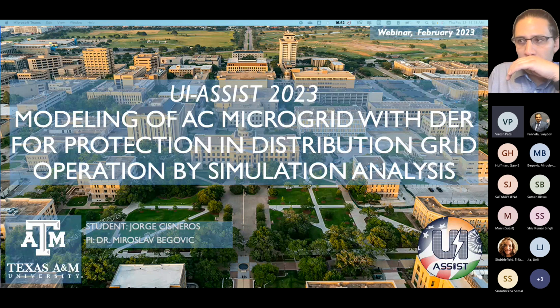Viresh, meanwhile, I see another question from Suman Biswal. He's asking, as the two systems are geographically isolated, does it affect the performance of the simulation? Yes, there was a communication delay, so we had to take care of it. For that, we got a direct connection between the two RTDS using the port binding method. With the number of data packets we tested, we found that 100 data packets was the optimal number, correctly simulating the event on the other side. It was reflecting perfectly fine.